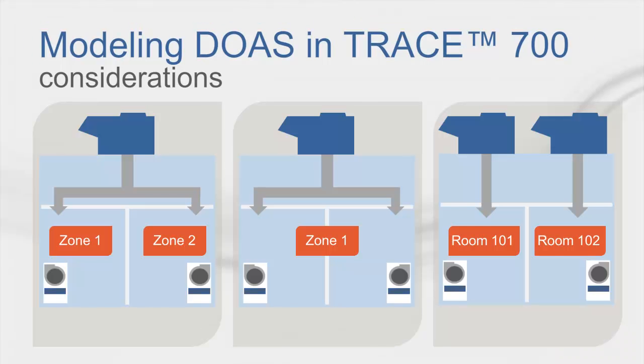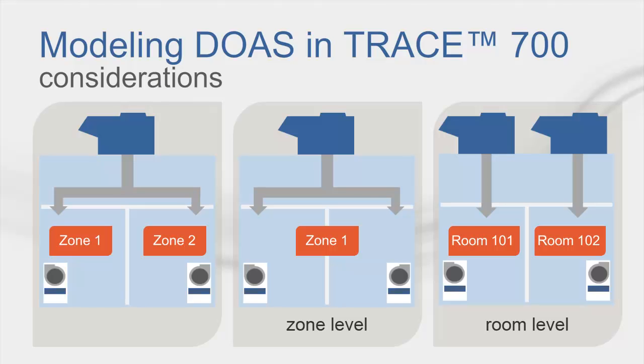Second, the dedicated outdoor air coil can be set to system, zone, or room level. The coil level dictates where the dedicated ventilation unit or units will be placed, as shown in these three diagrams. For example, if system level is selected, all zones within the system will share the same DOA. However, if room level is selected, each room will get a separate DOA.